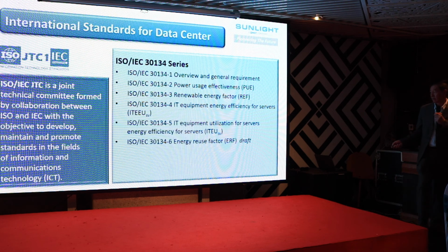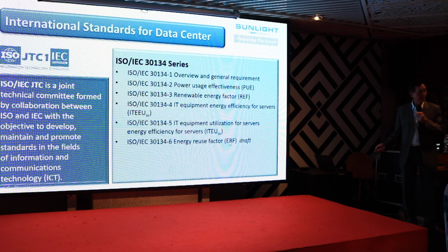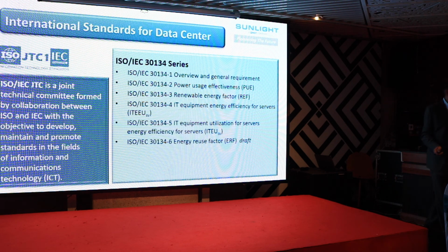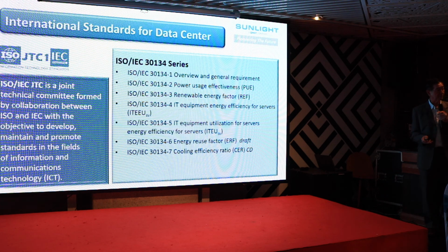It's at the moment in the draft stage, not yet a published document. But once confirmed, in short what we call the FDIS, the final draft standard, becomes Part 6 as a document. Part 7 is cooling efficiency ratio. This will be very interesting for mechanical disciplines. Currently, it is in the committee draft. That is not available. If you are not in the committee drafting the standard, you won't get to see it until it is distributed to the national committees, who start to comment and vote on it. So only the committee members get to see it.